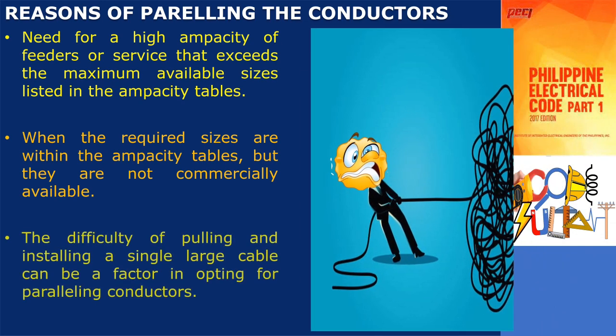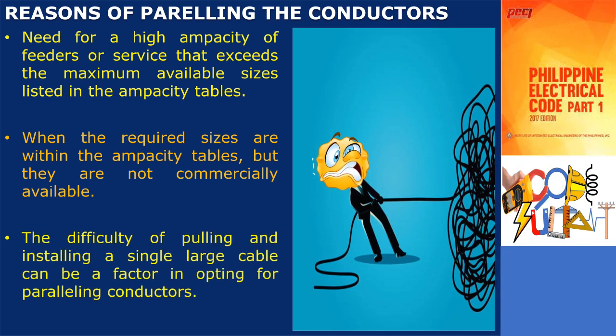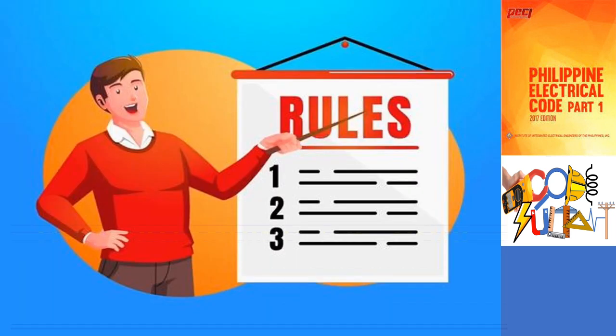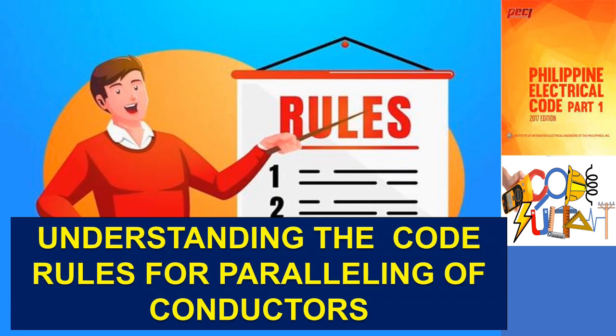Furthermore, the difficulty of pulling and installing a single large cable can be a factor in opting for paralleling conductors. Large cables can be challenging to handle, maneuver, and install due to their size and weight. Paralleling smaller conductors provides more flexibility and ease of installation while still achieving the required ampacity. For these reasons, a total understanding of the paralleling requirements permitted in the electrical code is necessary before attempting to design a large electrical system or install these conductors.